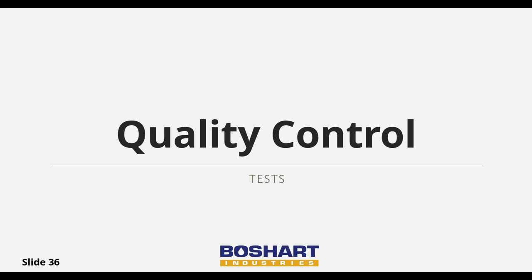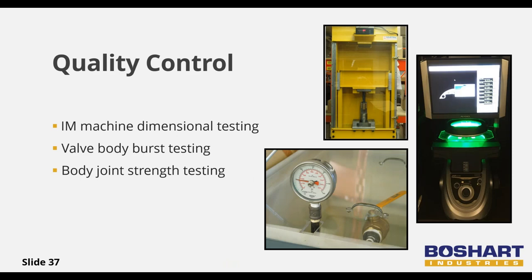Here at Boshart we conduct plenty of tests to ensure that our sump check valves are up to our standards. On products manufactured by Boshart, we inspect a sample of each piece using our CMM machine, which provides a quick dimensional inspection of each piece. We perform burst testing on a sample of the valve bodies to ensure they surpass our pressure ratings, and we also perform body joint tests using our tensile tester to inspect the body connection strength.